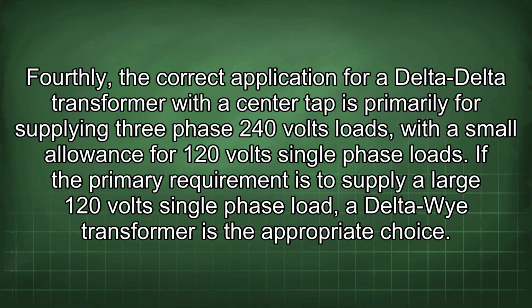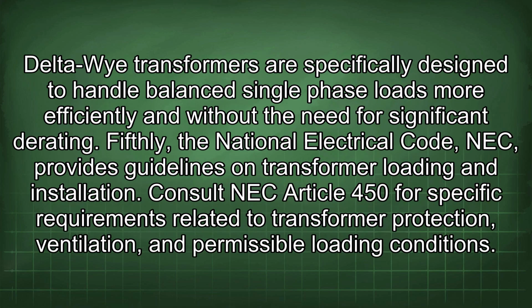Fourthly, the correct application for a delta-delta transformer with a center tap is primarily for supplying three-phase 240 volts loads, with a small allowance for 120 volt single-phase loads. If the primary requirement is to supply a large 120 volt single-phase load, a Delta-Wye transformer is the appropriate choice. Delta-Wye transformers are specifically designed to handle balanced single-phase loads more efficiently and without the need for significant derating.